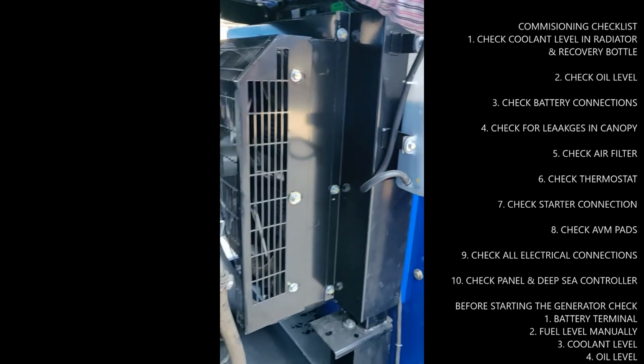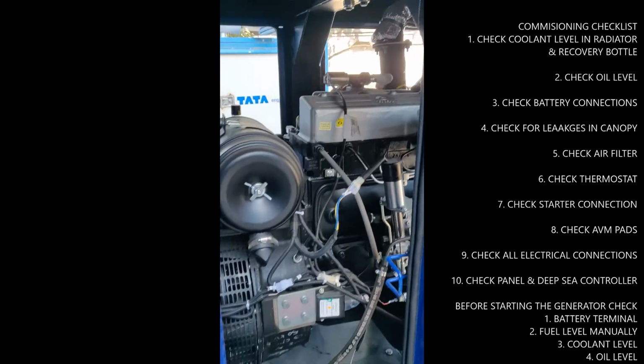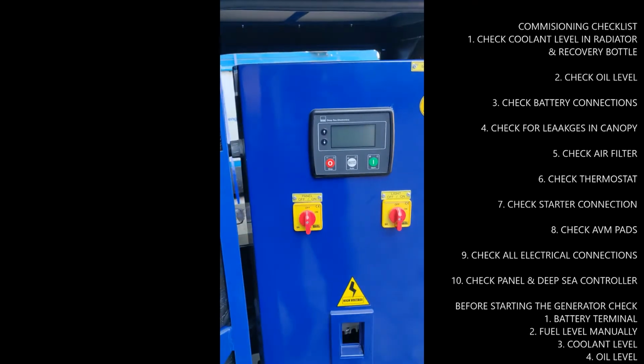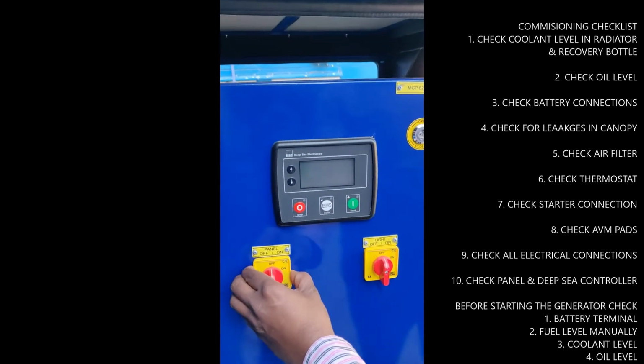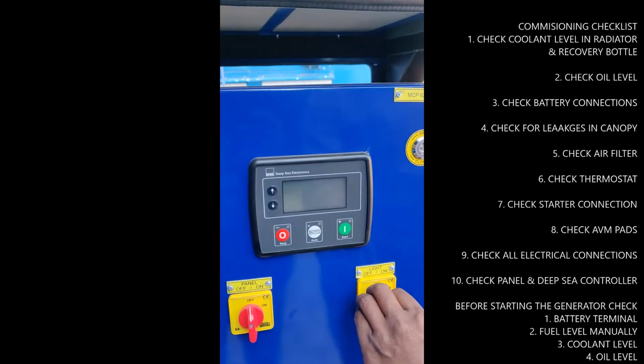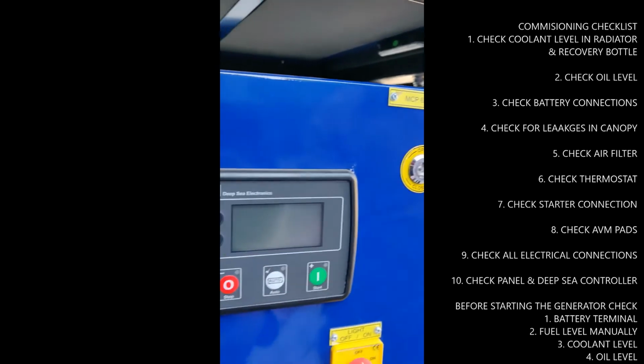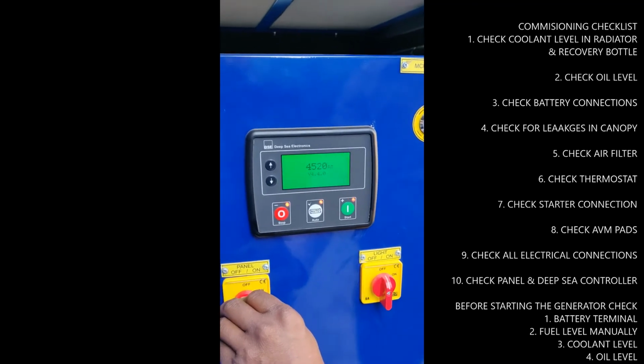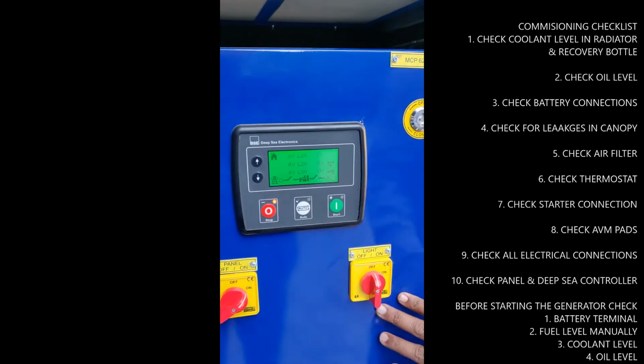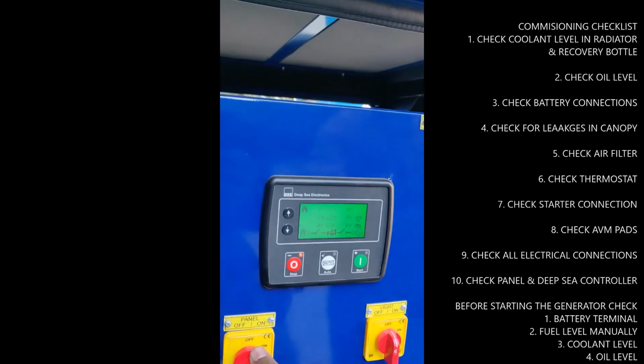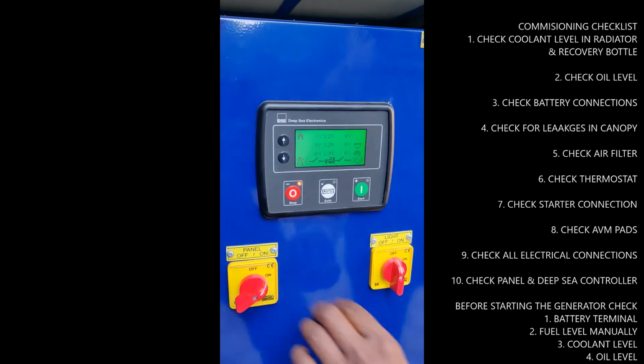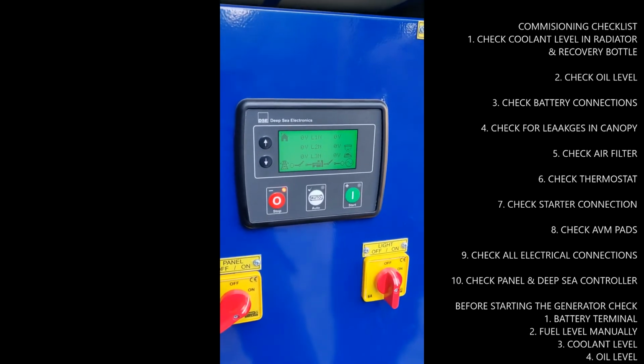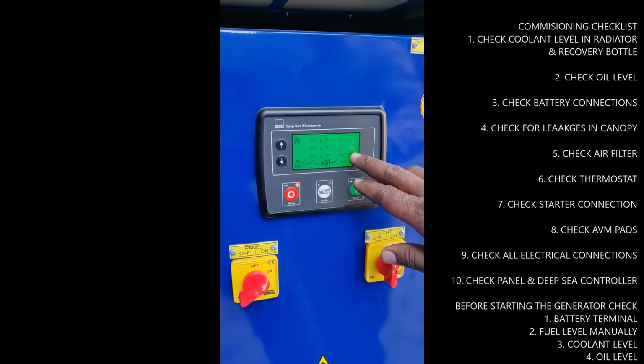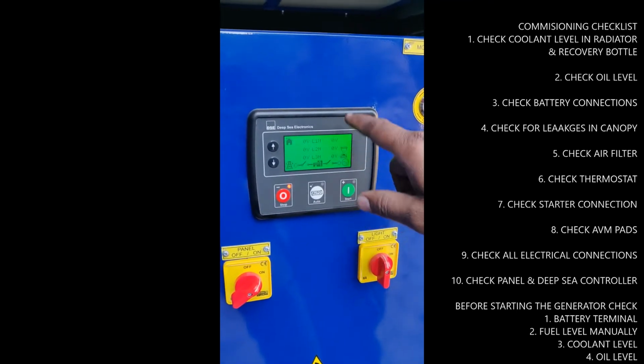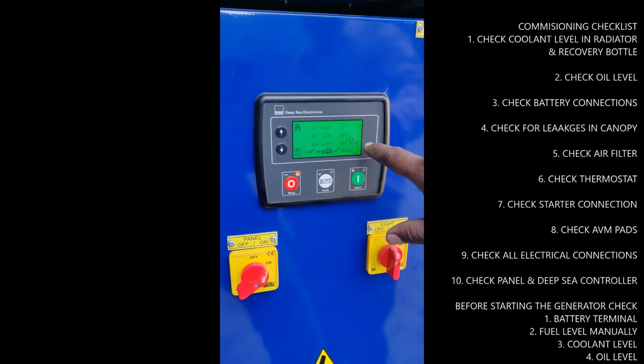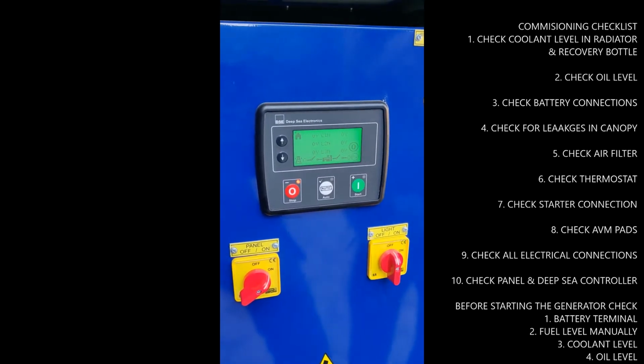Once all of these things have been completed, you can now switch on the panel. This is the panel switch on, and we have the light of the generator also. The light of the generator gets on from this switch. We have turned on the panel now. Wait for the panel. There is a timer, as you can see in the controller. Wait for the controller to reset. It takes approximately 10 seconds for the controller to reset. Once this loading sign is off and you see a 0, the genset is ready to start.